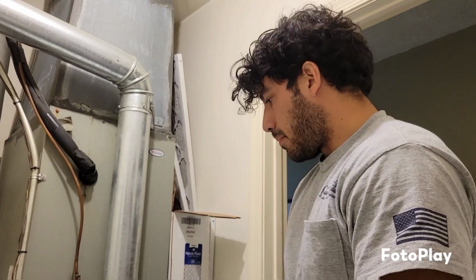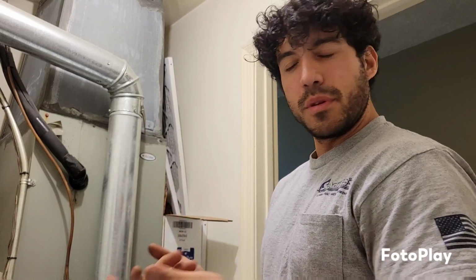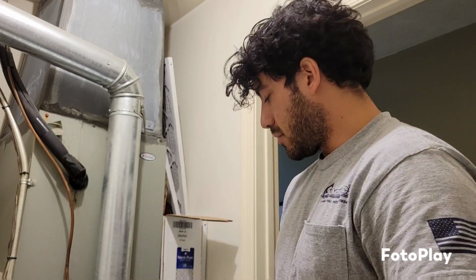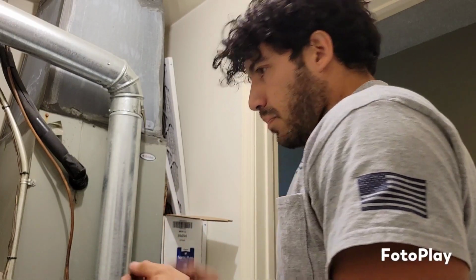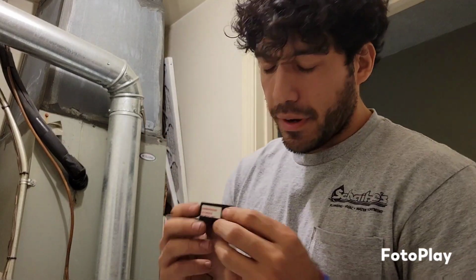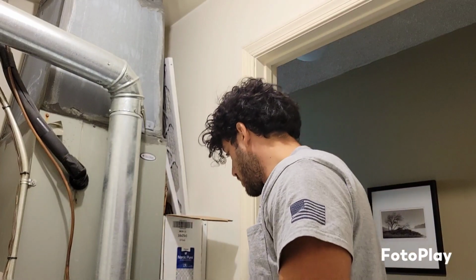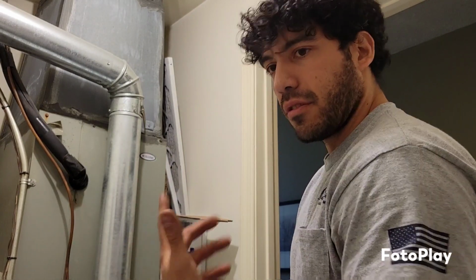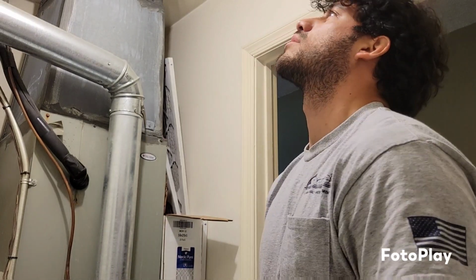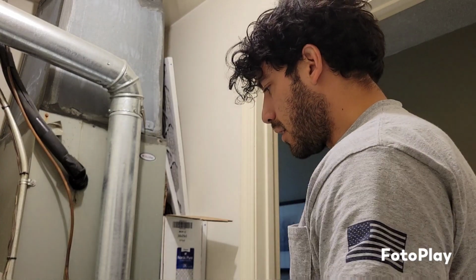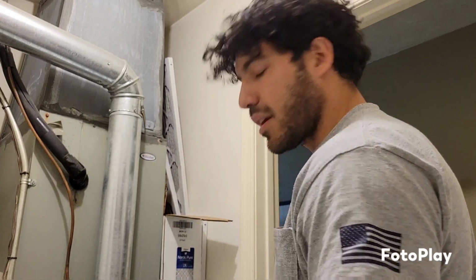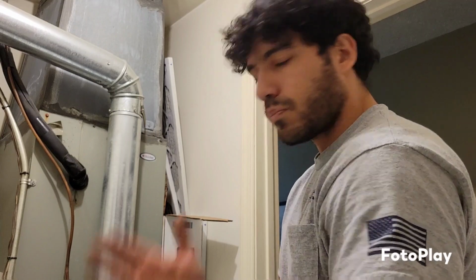Yeah, but that was kind of an easy thing to diagnose and see. It's not your typical board that you're running into, just because it has all these communication modules and little interfaces that you have to make sure you plug back into the right spots. And then there's this guy right here, which is basically the brains of the unit and tells it what it is. I'm gonna keep an eye on it, make sure my split is good as far as temperature rise, because right now it's running at 100% capacity, since that W2 terminal was jumped out. So I'm gonna keep an eye on it, make sure it's fine, and it should be good to go.